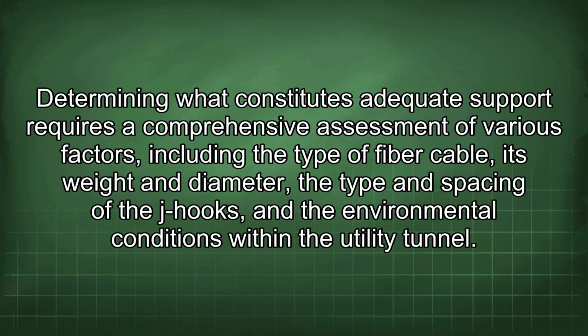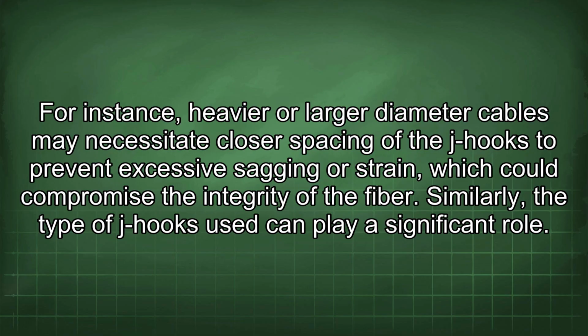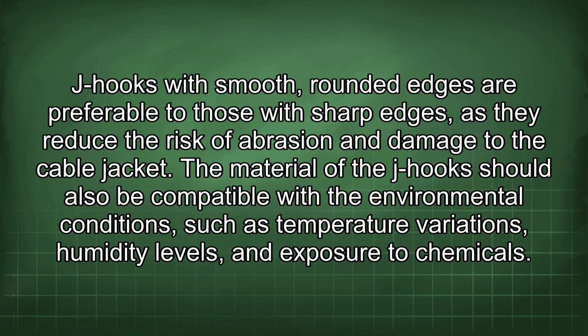Determining what constitutes adequate support requires a comprehensive assessment of various factors, including the type of fiber cable, its weight and diameter, the type and spacing of the J-hooks, and the environmental conditions within the utility tunnel. For instance, heavier or larger diameter cables may necessitate closer spacing of the J-hooks to prevent excessive sagging or strain, which could compromise the integrity of the fiber. Similarly, the type of J-hooks used can play a significant role. J-hooks with smooth, rounded edges are preferable to those with sharp edges, as they reduce the risk of abrasion and damage to the cable jacket.